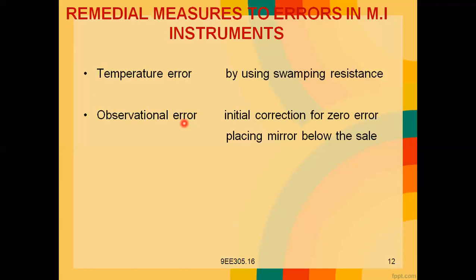And I go and try to measure a current whose true value I already know, say 2 amperes. My meter should be showing 2 when I connect it, but because it is not adjusted to 0, it was showing 0.5 before connecting. Now I'll be seeing 2.5 amperes instead of 2 amperes.